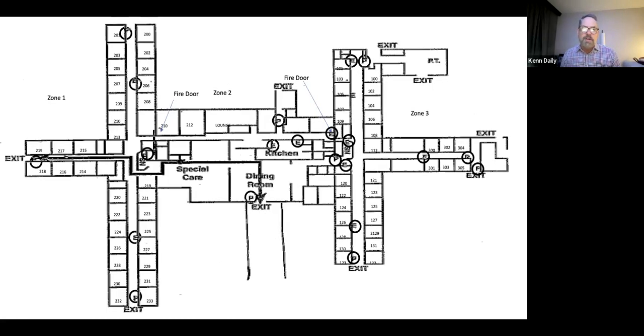This drawing is a really simple drawing. I put P's and E's for pull stations and fire extinguishers. And you'll see I didn't do a good job on this one of showing where the fire doors are. I really need to update this and show where the fire walls are. Obviously, the walls are continuous along with where those fire doors are, but I do identify the 3 zones of the building, so that the surveyor would be able to understand where different parts of the facility are, and all the room numbers are identifiable as well. Just having a clear drawing is going to be important for surveys going forward.